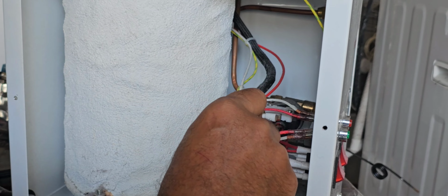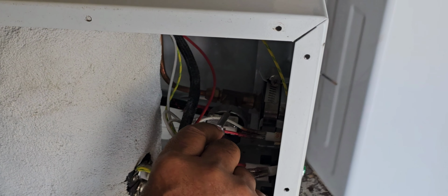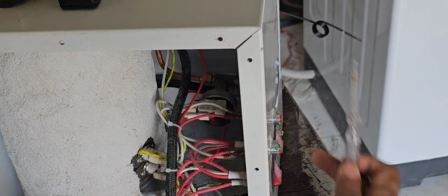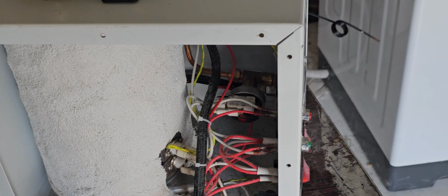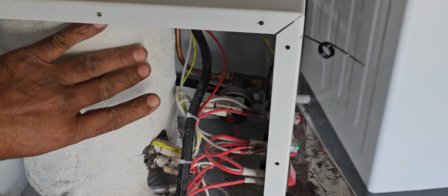This thermistor is also here. This is the thermostat. See here, this is the thermostat, with a micro switch. This is the steam generator thermostat, and also here you can see the pressure meter. This one we have to check A to Z now. This heater and thermistor, also here the thermostat. After that we can recognize what exactly the problem is.